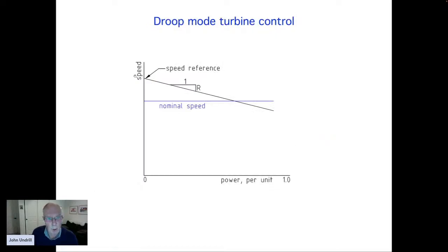When we talk about controlling the power system, we're talking about the ability to control the power flow on lines and the frequency of the voltage wave, and we control those by controlling the speed and the power of rotating generators. The control of a generator is delegated to the governor. The governor does not control speed, and it does not control power. It controls the relationship between speed and power.